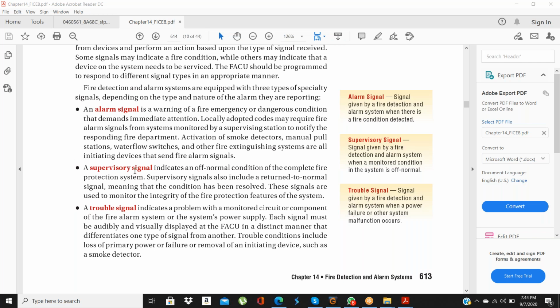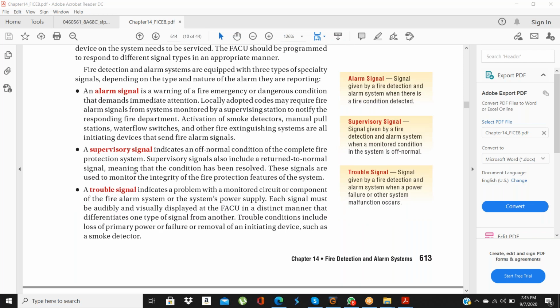Yes. Please tell us, does the supervisory signal do the work if there is a fault, then the supervisory signal will alarm? No, the supervisory signal is just supervising the system, whether the systems are okay or not. Once there is any trouble, let's suppose someone removes the smoke detector, or someone removes the sprinkler, then the trouble signal will send the signal to the central unit system. It will not say that someone removed it, but it will show that the fire detector is missing. It will also give you the zone detection. Okay, now clear. Thank you.